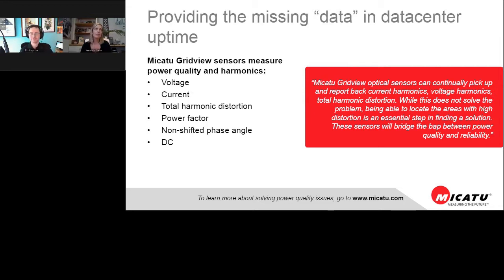Yeah, the name of the game is really power quality. It's interesting because when it comes to sensor and metering technology on the power side, we've been doing it the same way for 100 years. You're either using an instrument transformer, or more recently, something like a line post sensor. Both of those are electrical circuits, transformers that step power down to a level that metering equipment or relays and controls can handle, because if you put 12,000 volts across a relay, it's going to blow up. We like to blow things up in the power industry, let's just get that clear.